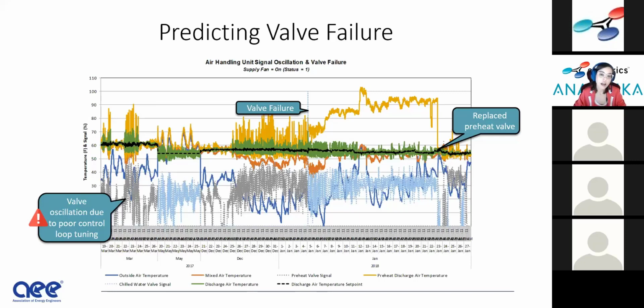An old colleague of mine used to call these insidious faults, and I really like that term because it would go undetected. You wouldn't get a hot or cold call. You would never know that this was happening. You'd still meet your temperature, and you would be wasting a ton of energy, and it is not how the system is intended to run. They replaced that valve, and we're working on the loop tuning.